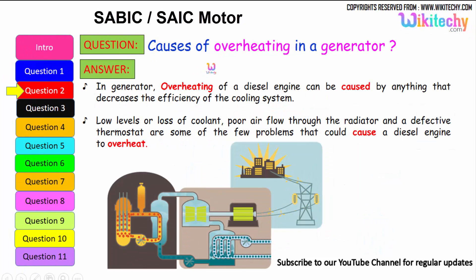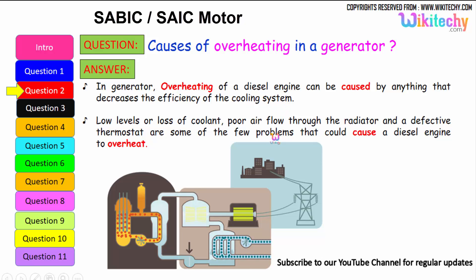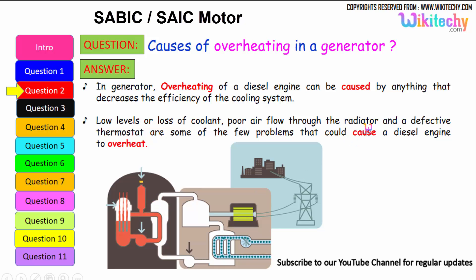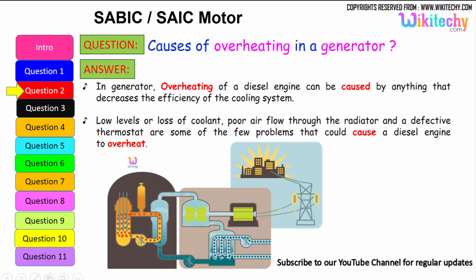Let's move on to the next question: causes of overheating in a generator. Overheating of a diesel engine can be caused by anything that decreases the efficiency of the cooling system. It can be due to loss of coolant or low levels of coolant, poor air flow through the radiators, and a defective thermostat — these are some of the problems that could cause a diesel engine or generator to overheat.